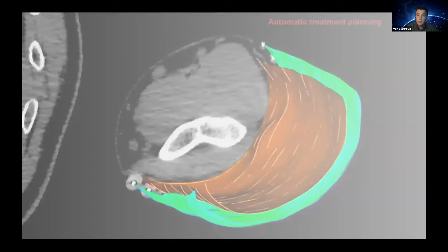I said that we decided not to print applicators because currently the Freiburg Flap or Varian surface applicator set, the blue one, or also the MIC applicator is still pretty good to be used for skin, with no need for special QA. And we decided to print the applicator holder as the immobilization device that we will place the applicator into. So what is the benefit of that? The benefit is when you scan the patient, when you put the flap applicator on, and when you process the information based on the CT scan, you know the geometry of the flap applicator. When you know the geometry, you know exactly the position of your catheters and the position of your 12 points.